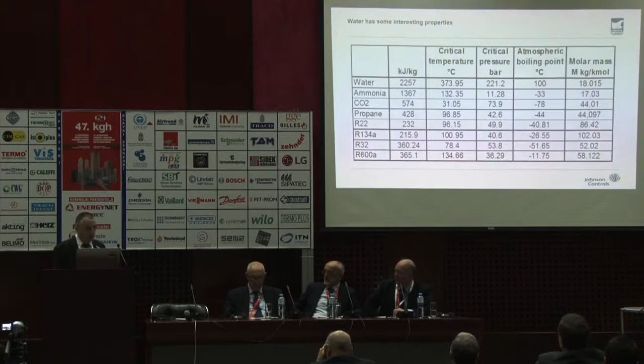The big problem with water is, especially at low temperatures, it is in deep vacuum, 0.006 bar, so we are close to the triple point. If we go to, for example, minus 6 degree water, it is a difficult task to have. As you also know, water boils at 100 degrees at atmospheric pressure, so it's good as a heat pump fluid, and we are looking at heat pumps for 130 to 180 degrees C at the moment.